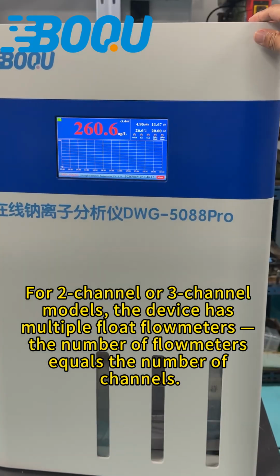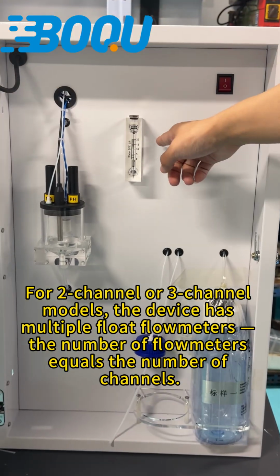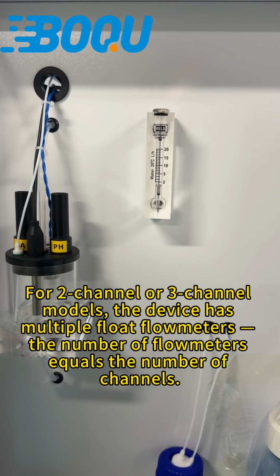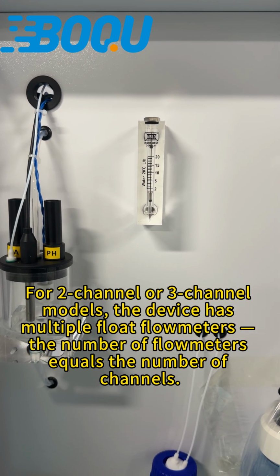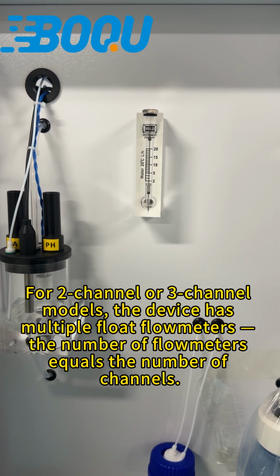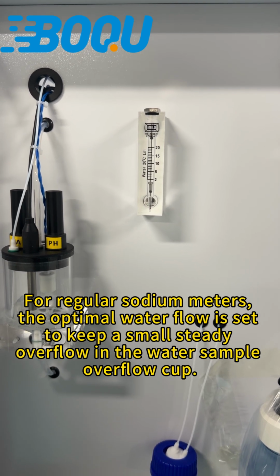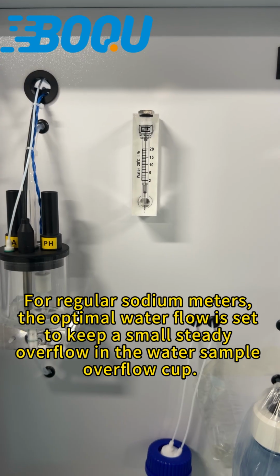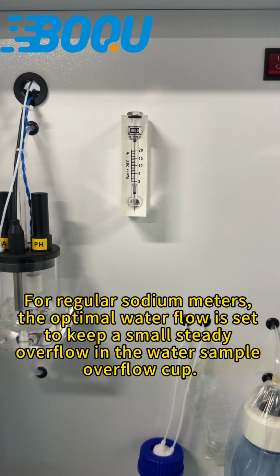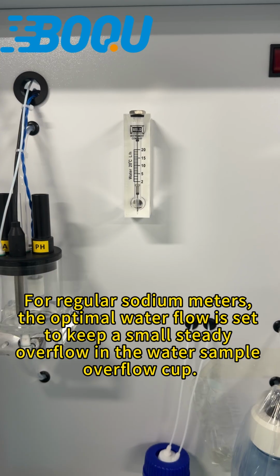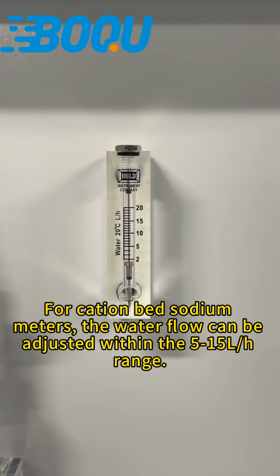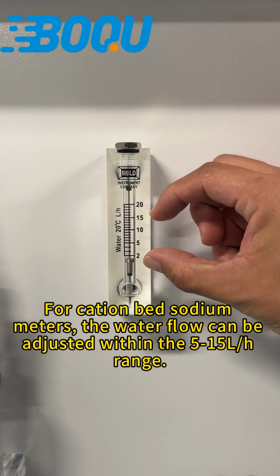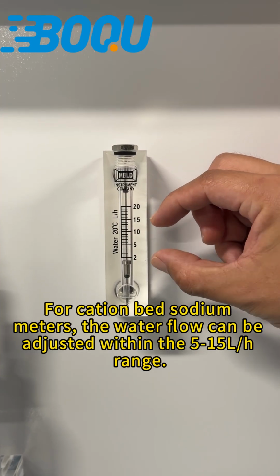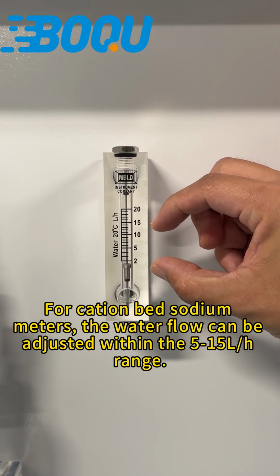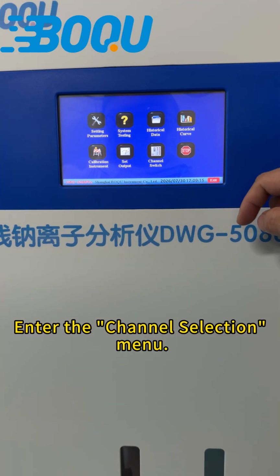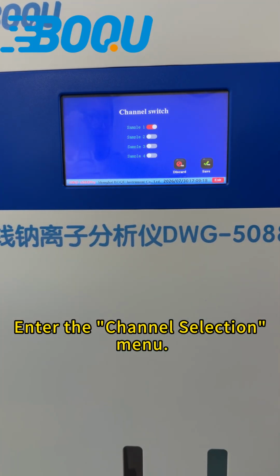Channel setup. For 2-channel or 3-channel models, the device has multiple flow meters. The number of flow meters equals the number of channels. For regular sodium meters, the optimal water flow is set to keep a small steady overflow in the water sample overflow cup. For Cation bed sodium meters, the water flow can be adjusted within the 5 to 15 liters per hour range. Enter the channel selection menu.